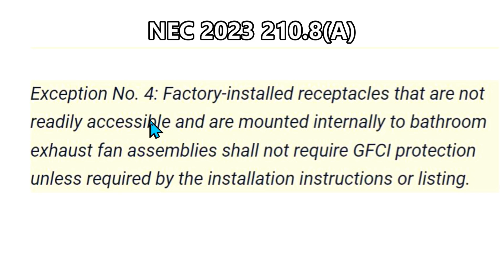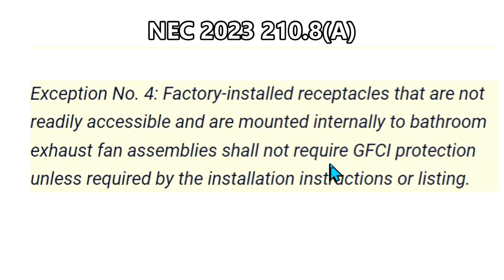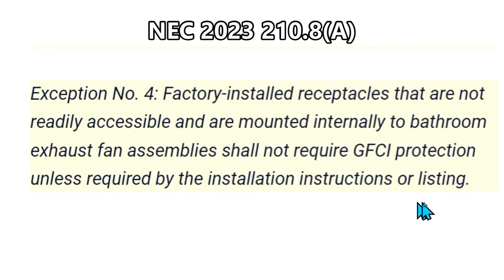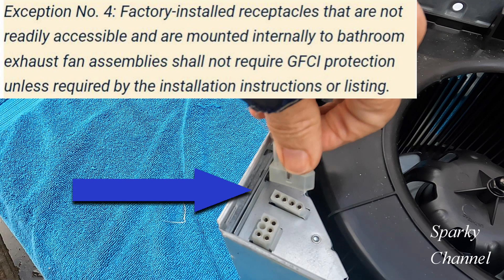Exception number four states: factory-installed receptacles that are not readily accessible and are mounted internally to bathroom exhaust fan assemblies shall not require GFCI protection, unless required by the installation instructions or listing. This is the factory-installed receptacle that is not readily accessible, which is mounted internally to the bathroom exhaust fan.